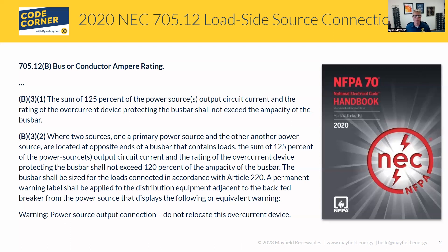B31 is a rare situation, but it does happen. B32 is really the one we see applied almost universally. What B32 is saying is if you have a panel board with two power sources — a primary power source, the utility, and a PV system — this applies. And 705.12 is a more generic code section, but we're going to talk about PV systems here.